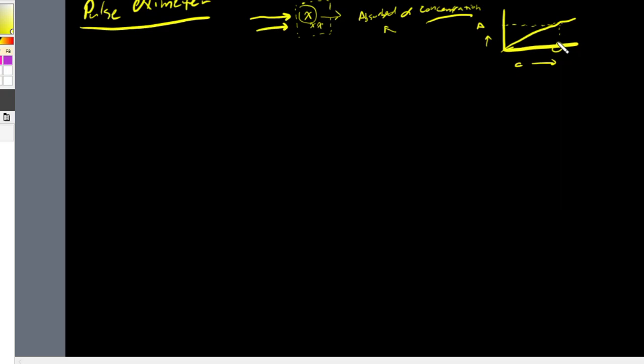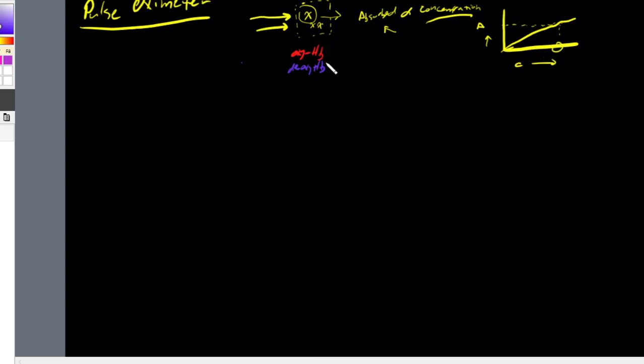Our pulse oximeter works on basically the same principle. It detects the amount of oxyhemoglobin — hemoglobin attached to oxygen — and compares it with our deoxyhemoglobin, the amount of hemoglobin that is unbound to oxygen. It shoots light through both of these substances at differing wavelengths, and based on the absorbance of light, it can determine a concentration and therefore an oxygen saturation.